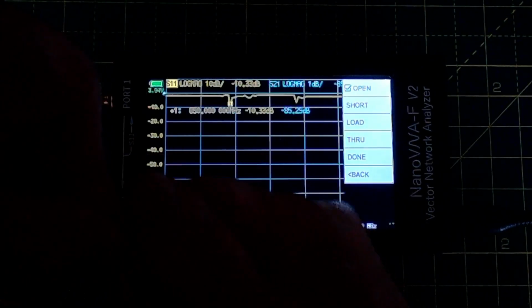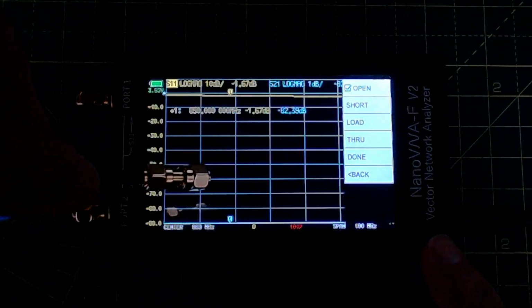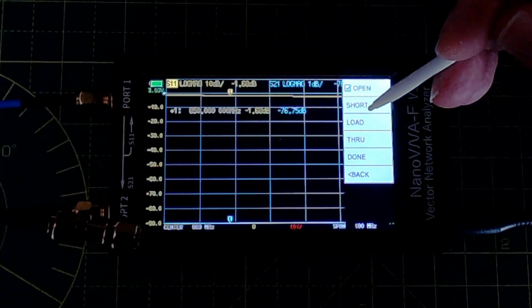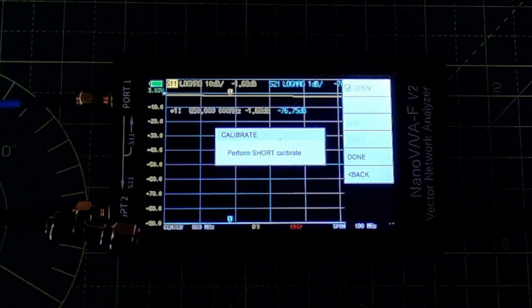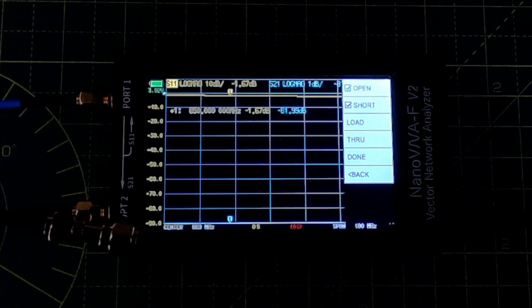So I'm looking in the plug to make sure this really is the short circuit plug, and it has a small pin in the center to make a real short circuit. If I move the cable, you can see that's on there now. That's the short circuit plug. So we press short for short circuit. The very reassuring beeps. So that's done as a check mark.